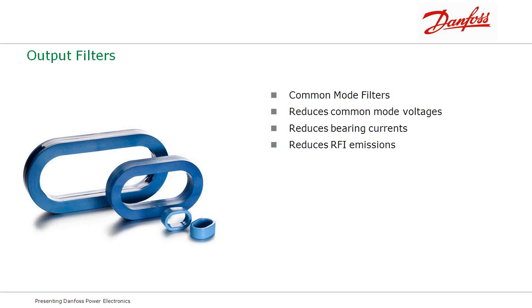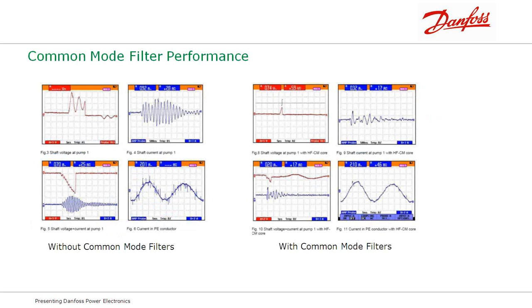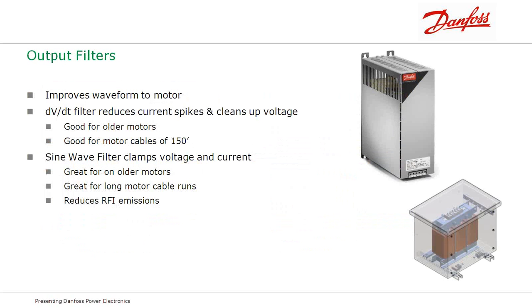And when you have issues of bearing currents and other issues, we can utilize these common mode filters, which mount around the wires, and you can see here on the left and the right. Without the filters is on the left, with the filters is on the right, and does a phenomenal job of reducing the bearing currents, stray voltages, and for those of you in Europe, reducing the RFI generated by the drives.